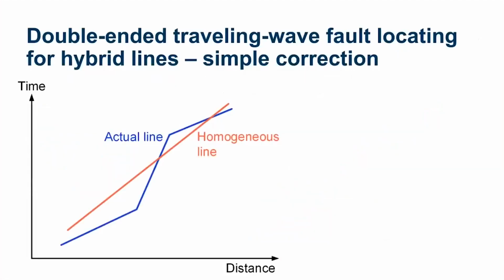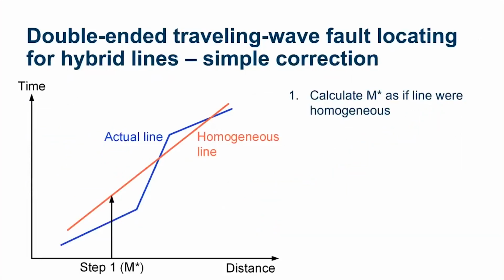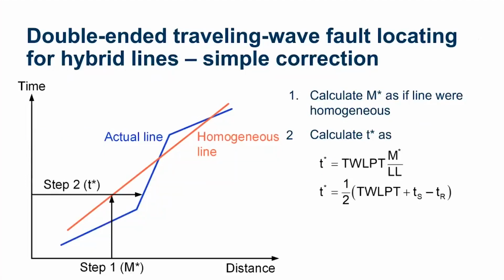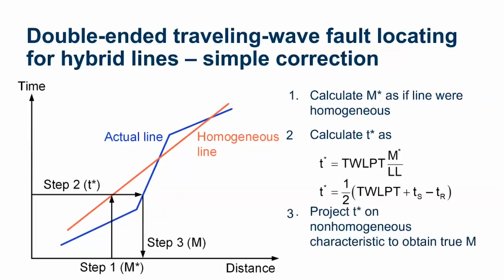So let's go to the slide that goes through the steps. Again, we have a fault. Step one is to calculate the fault location M as if the line were homogeneous. Then I'm going to calculate my T prime, which is the time it took for the wave to get there as if the line was homogeneous. I'm going to project that T prime to the non-homogeneous characteristics of the hybrid line, and then we're going to calculate the true fault location M.